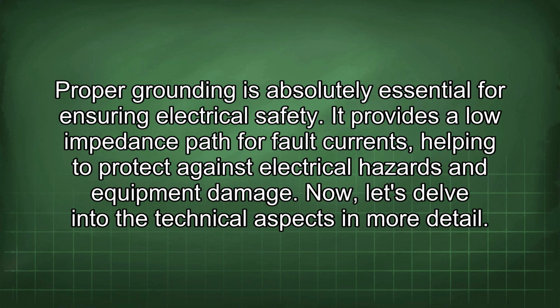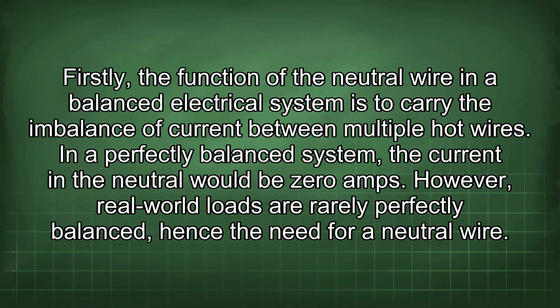Now let's delve into the technical aspects in more detail. Firstly, the function of the neutral wire in a balanced electrical system is to carry the imbalance of current between multiple hot wires. In a perfectly balanced system, the current in the neutral would be 0 amps. However, real-world loads are rarely perfectly balanced, hence the need for a neutral wire.